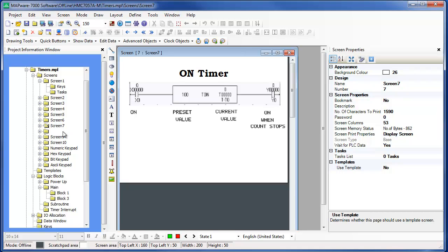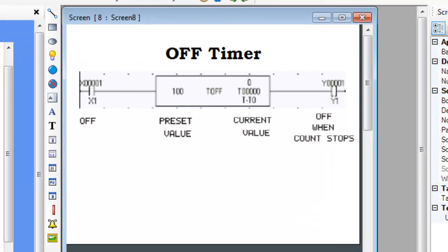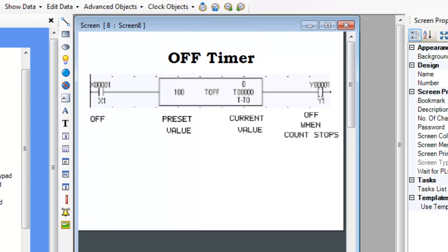The off timer counts while the input is off. When the preset time value is reached, the timer stops counting and the output turns off. Setting the input on resets the timer to zero and also turns the output on.